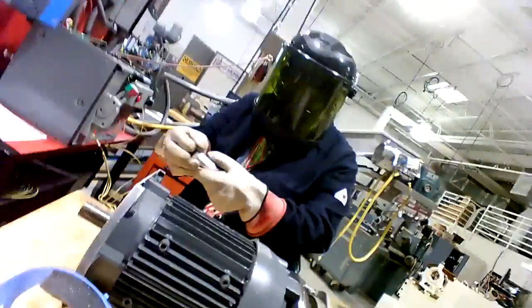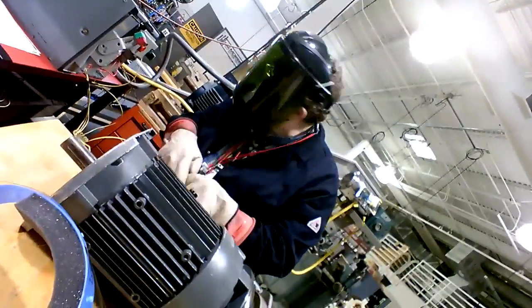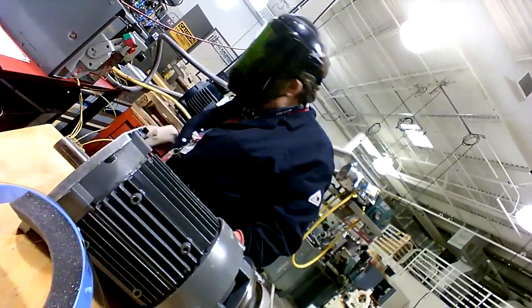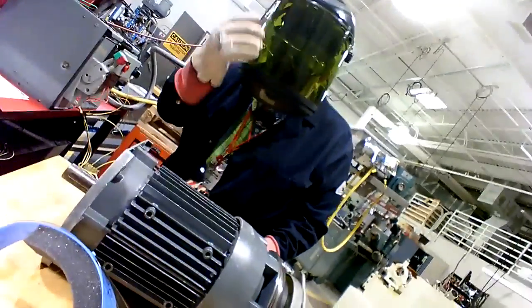And then we're going to check the amps. We're going to put an amp clamp on each one of these wires going to the motor, and we'll be able to show you that. We're putting the clamp on each phase conductor for the motor. So we're going to put the camera back around here, and I'm going to do the probing, and they're going to hold the meter and show you the numbers when we're doing that.